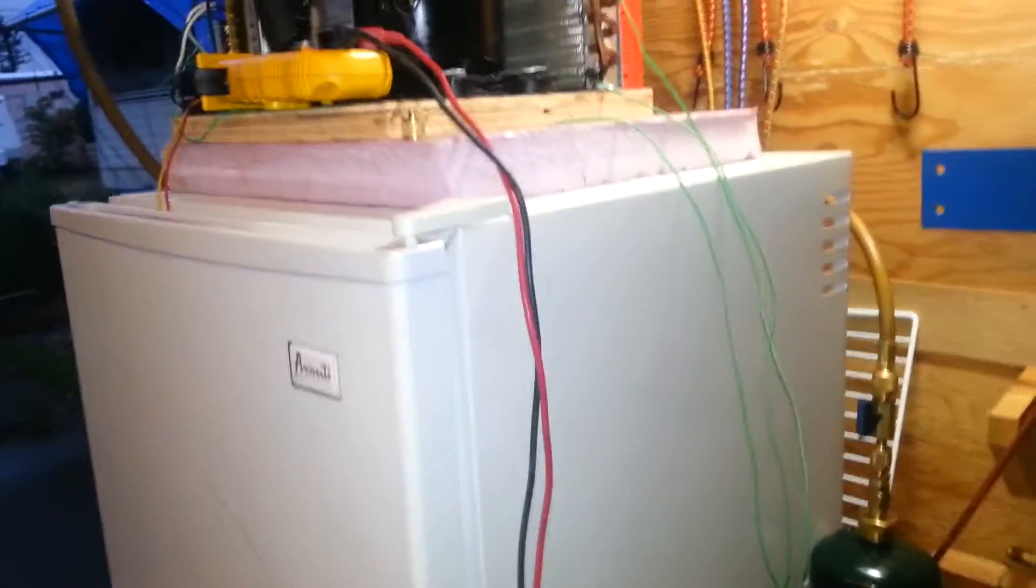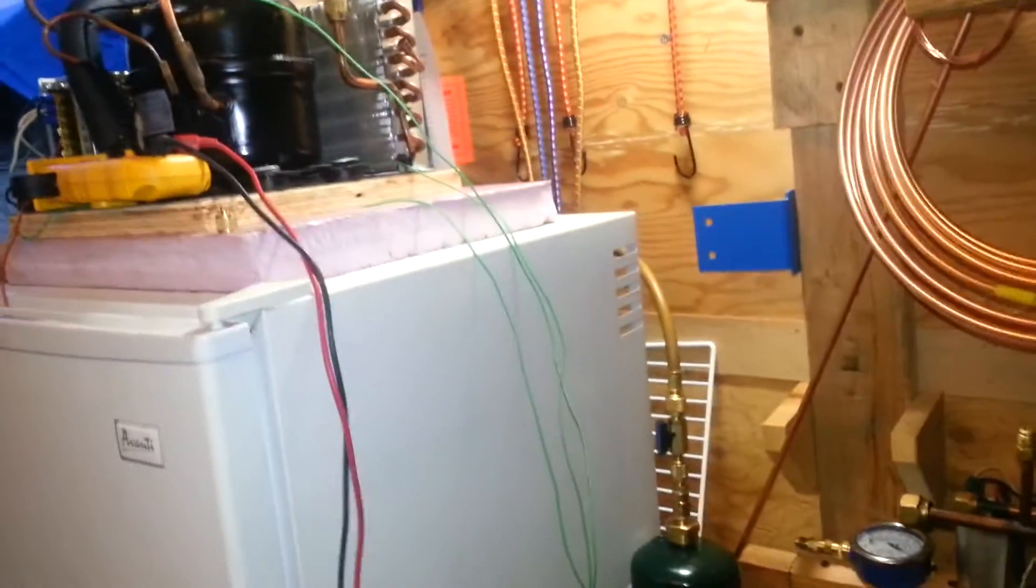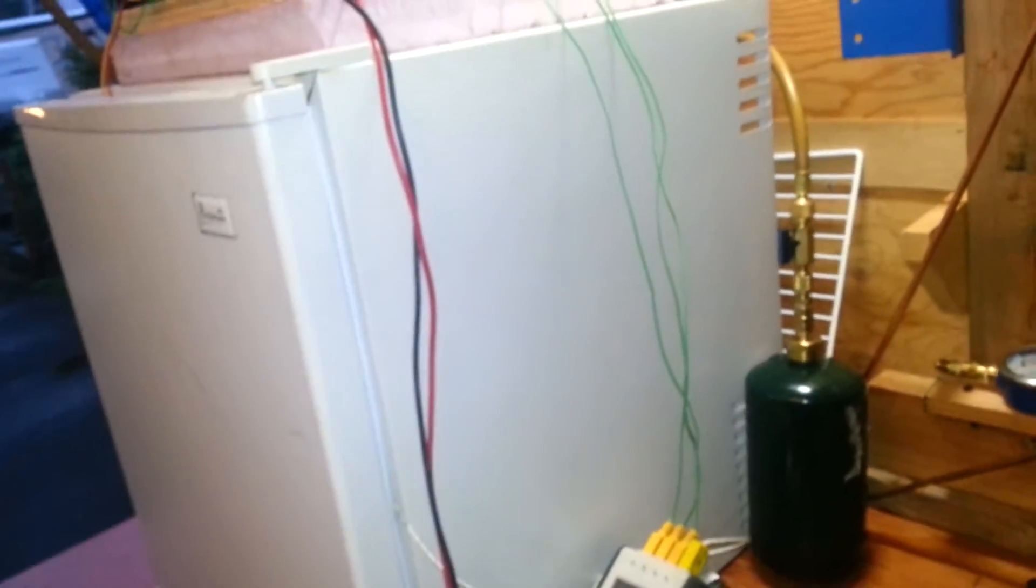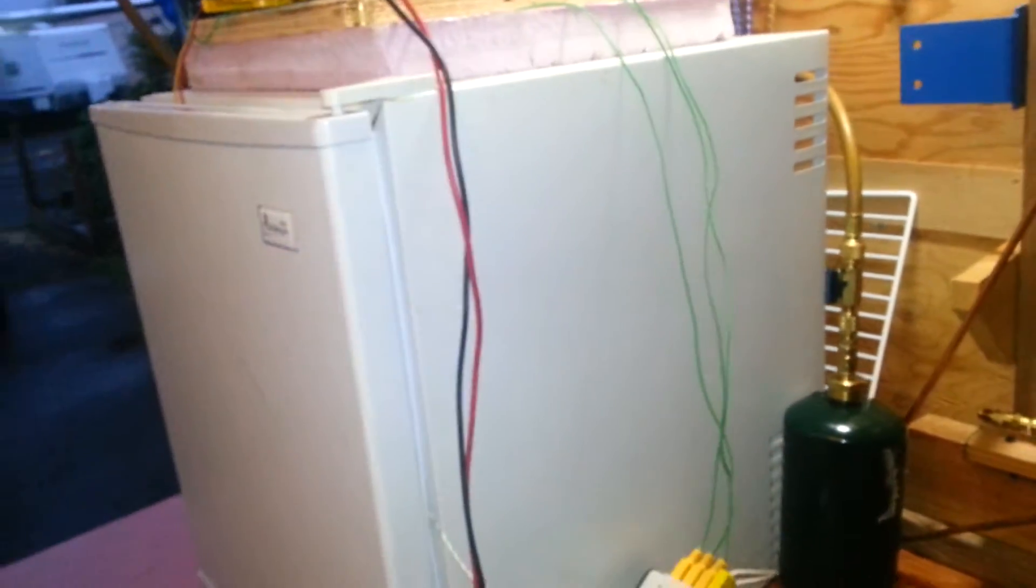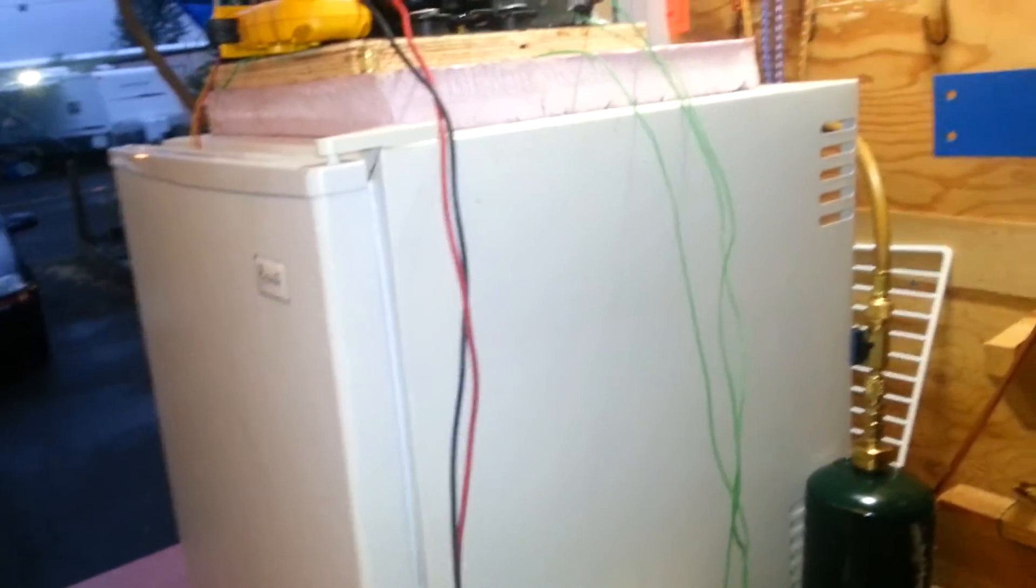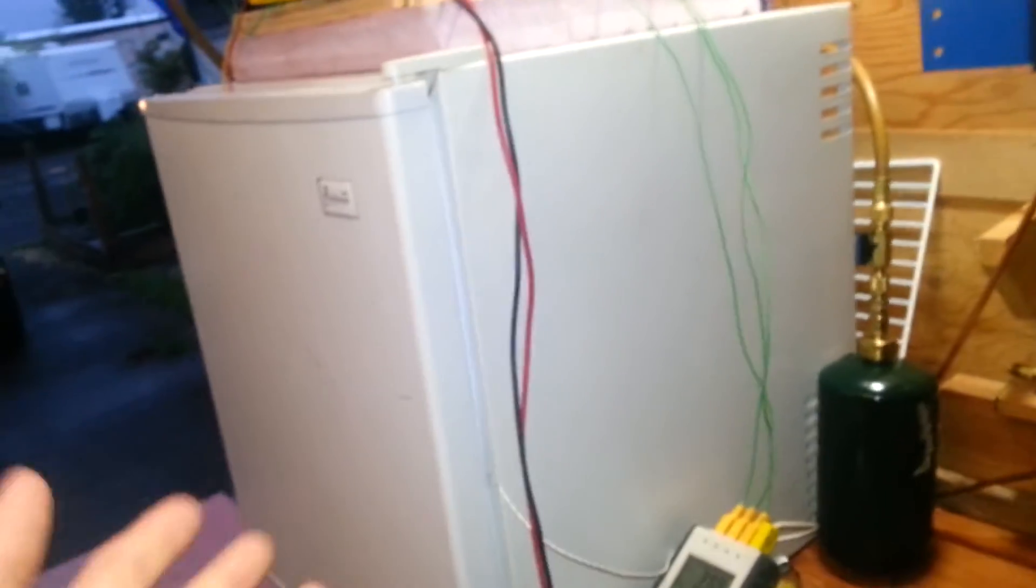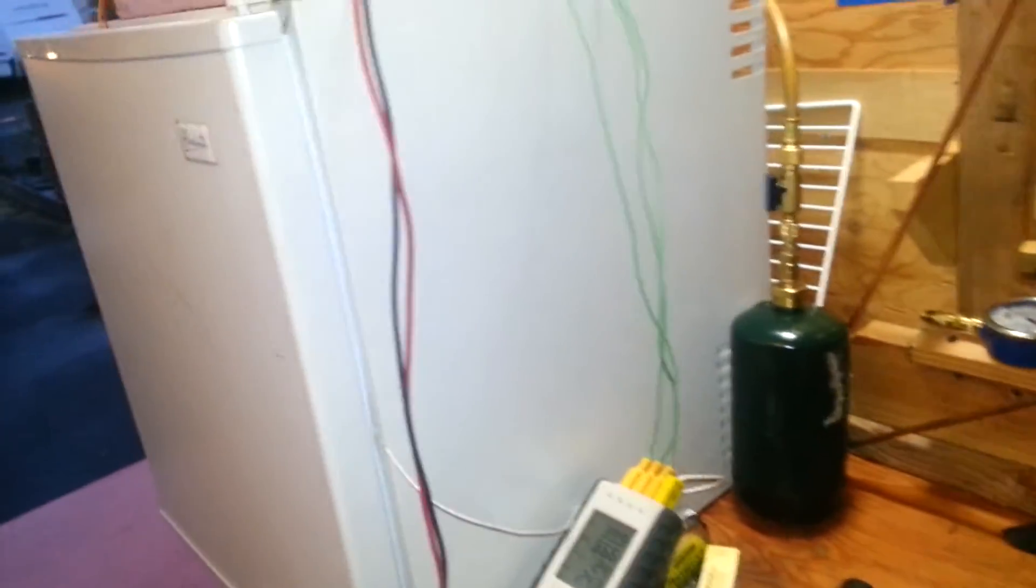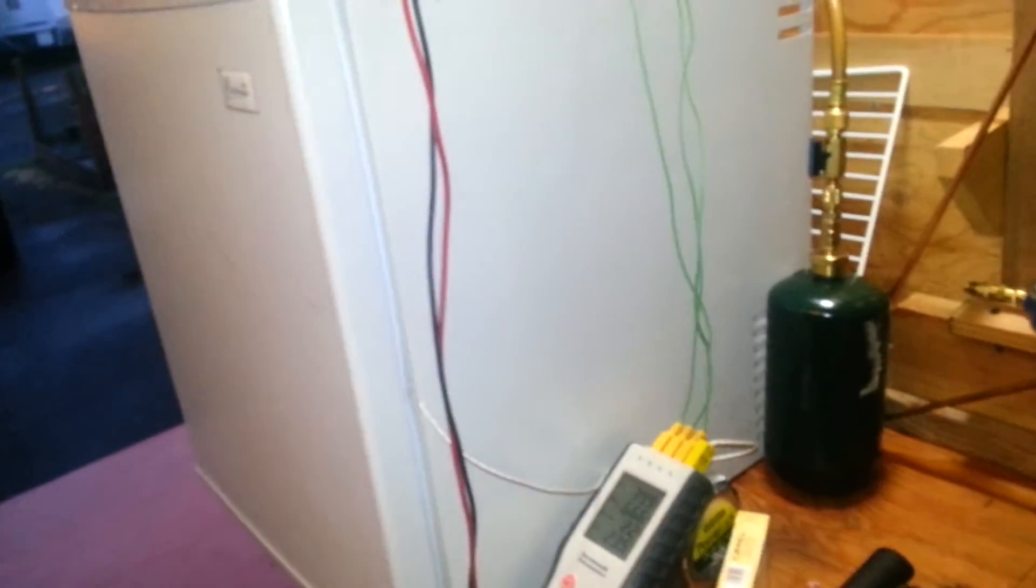I'm probably going to run it again a bit tomorrow. I'm going to do something a little bit different with it. I'm going to pull the glycol bucket out and just run the coil directly and observe that effect. I'm expecting the coil to freeze up pretty rapidly and the temperature in it to plummet. I'm probably going to get better refrigerating effect or really I'm going to be able to drop the temperature of the box down lower and do more cooling faster.